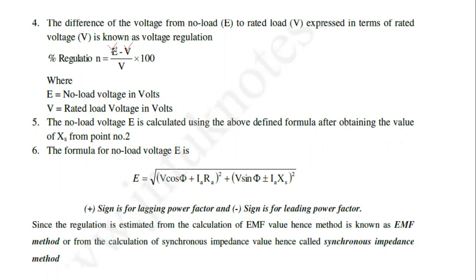Therefore, the percentage of voltage regulation is defined as the difference between the no load voltage and the full load voltage, divided by the full load voltage, into 100.